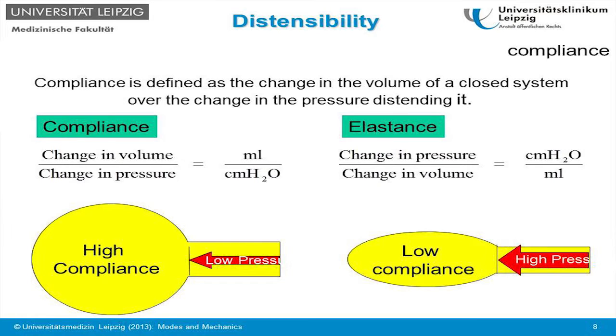To adjust the settings of the ventilator, we need to be aware of 2 things. It's the pulmonary compliance, the distensibility of the lung. The compliance is defined as change in volume by change in pressure, and the elastance is the reciprocal: the change in pressure you need for a certain change in volume. And with a low pressure and a high compliance, you get a much higher volume than with high pressure faced with a low lung compliance.